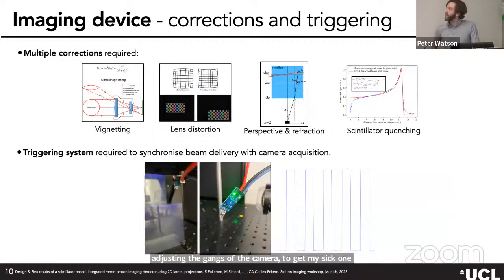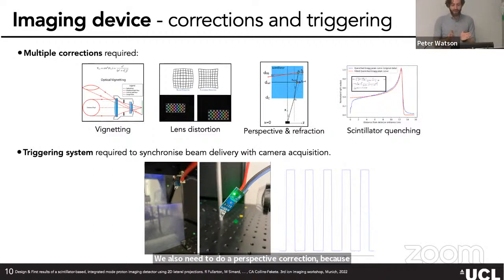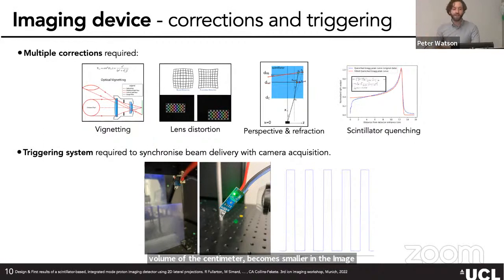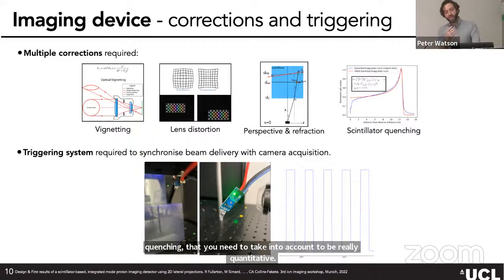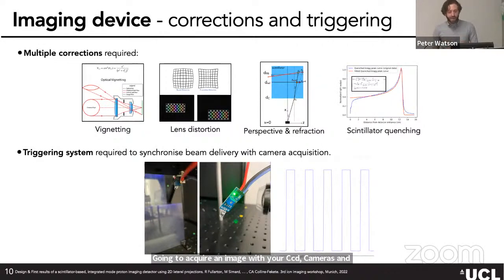Working with optical photons requires many corrections: optical vignetting, lens correction, perspective correction because the CCD field of view gets larger with depth, refraction correction, and scintillator quenching correction to be quantitative. We also needed to develop a triggering system to synchronize beam delivery with camera acquisition — ensuring that whenever the beam is shot from the source, the CCD cameras acquire an image at exactly that time.